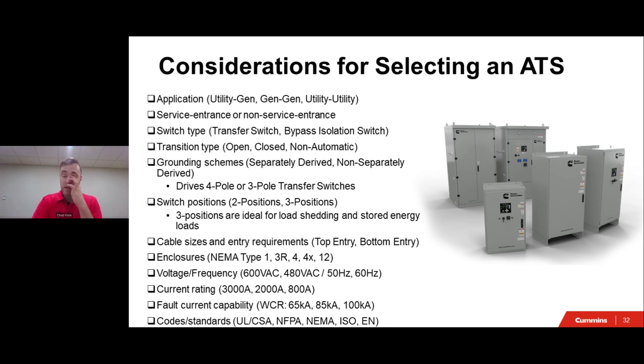So once again, is this a gen-to-gen application for prime power? Is this two redundant utility feeds, or is this just a normal emergency backup with a utility with a transfer switch in the middle between that and a genset? And then also understanding, are you legally required? Are you just optional? Are you a farmer that just needs a transfer switch? Things like that. And then also, based off of those factors, once again, what transition type do you need?